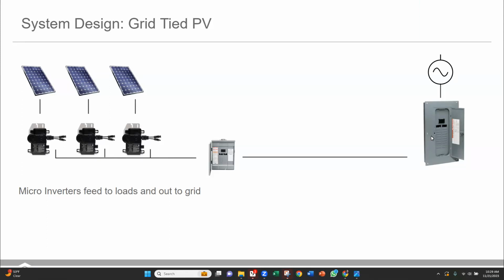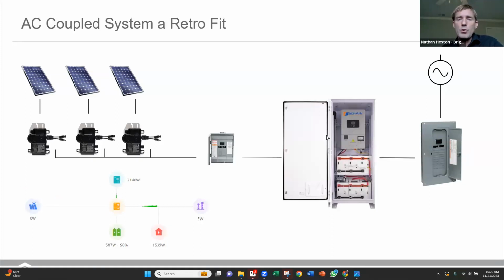We went from a net energy metering structure where a one-to-one kind of kilowatt hour to a net billing tariff where we're selling at a different rate than what we're buying at. And it's a much different rate to the point where it doesn't really make sense. You're getting pennies on the dollar to send those kilowatt hours that you generate back out to the grid. So it does make sense now to add batteries. So here's an example. The last thing you want to do is go out to a customer and switch around things and file an interconnection agreement and get them kicked off that more favorable rate, which they're grandfathered into.